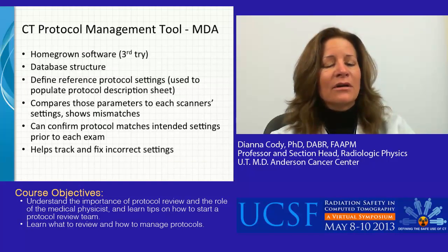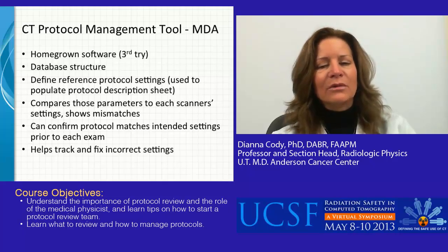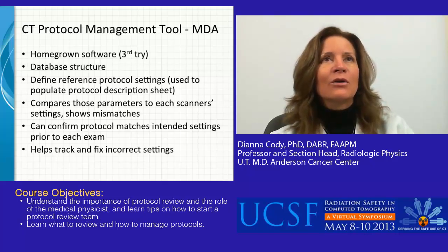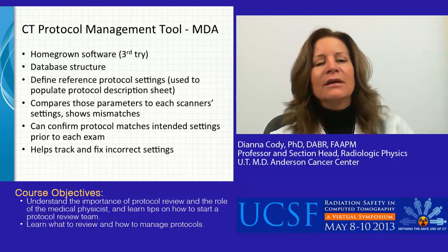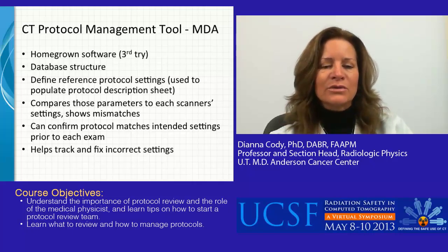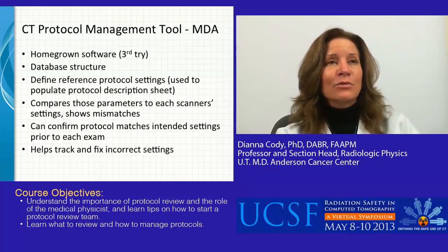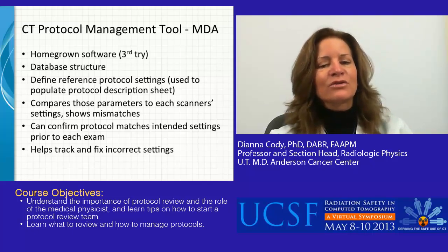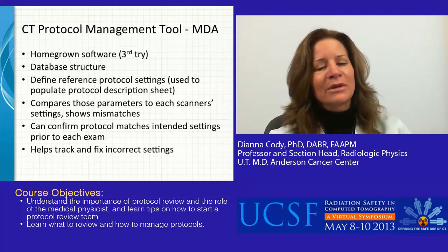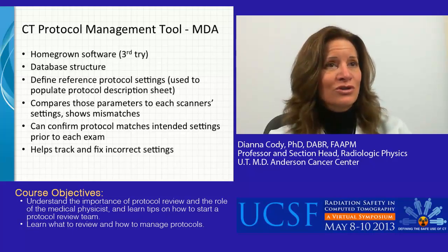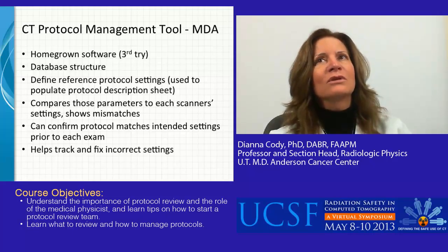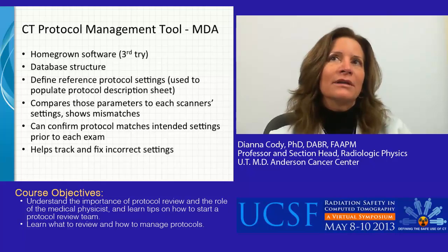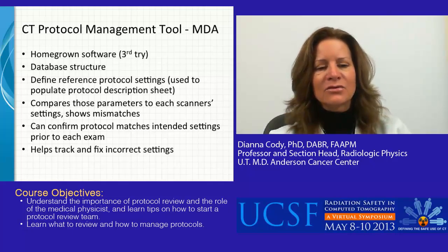We developed our own protocol management tool at MD Anderson out of desperation, basically. This is homegrown software. It was our third attempt. This time we're using a database structure, and we have defined reference protocol settings that are used to populate our protocol description sheets and are also used to check what is actually available on the CT scanners.